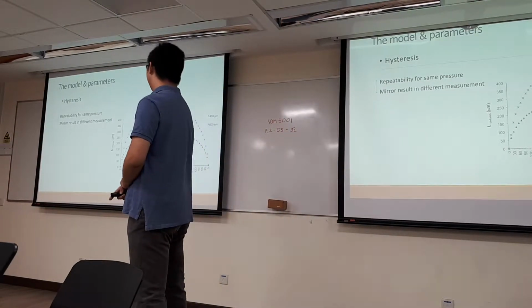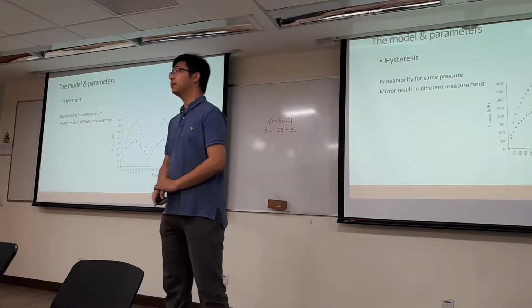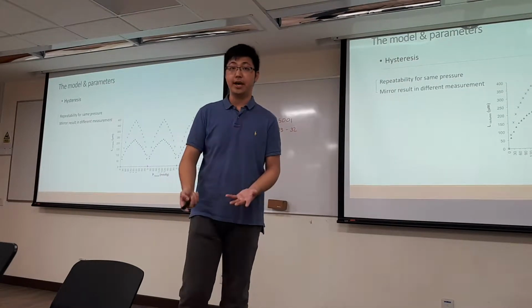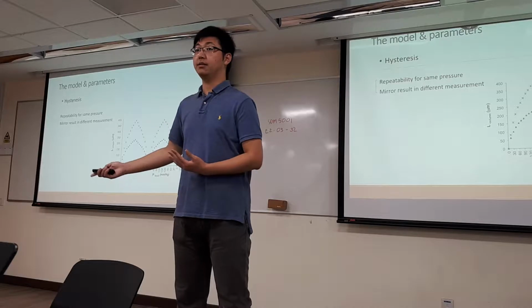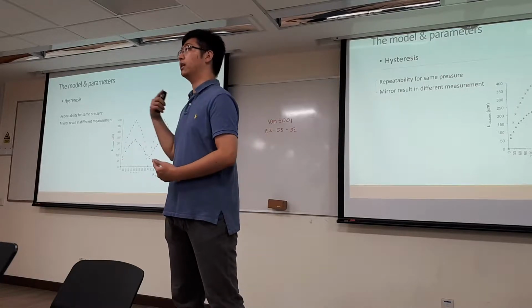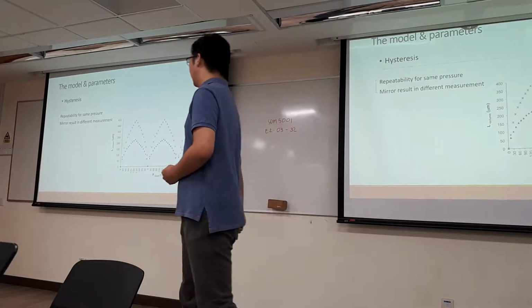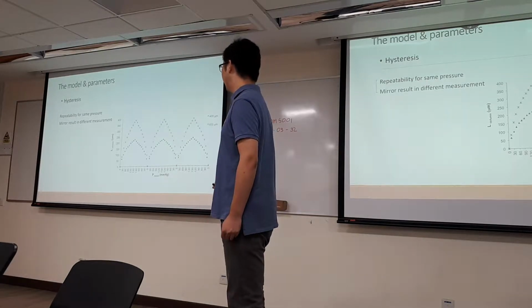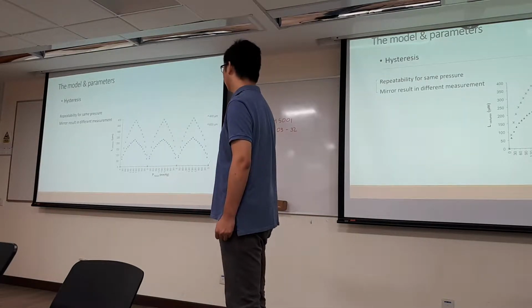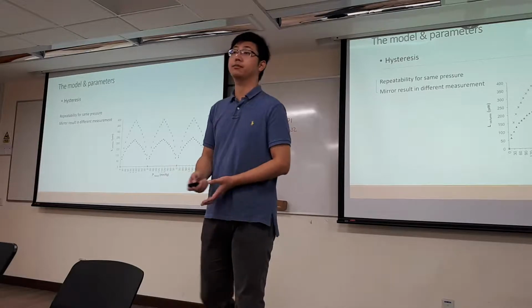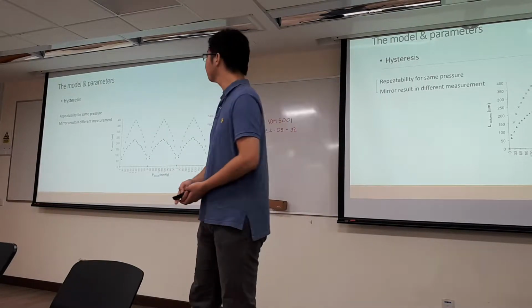The next one is the hysteresis performance, because we want to get the same result for the same pressure in different measurements, because it's a periodic measurement. We want to test it again and again and again. And of course, in this test, we can see that all the output curves mirror each other, which shows that the hysteresis performance is relatively good.